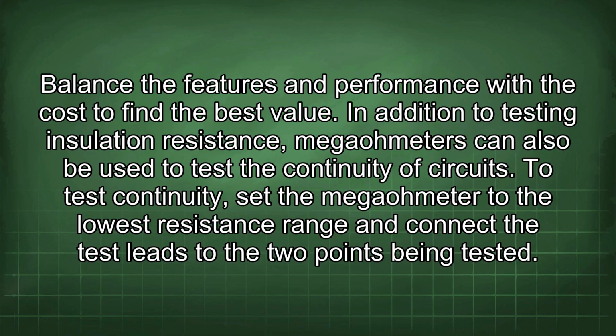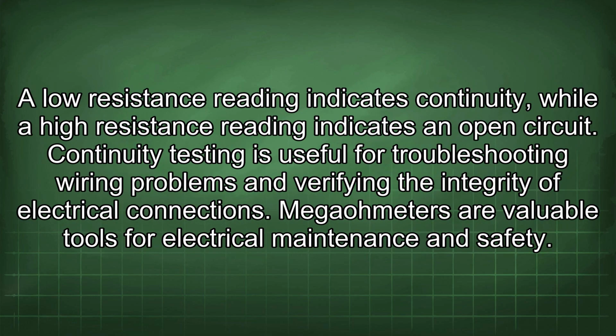In addition to testing insulation resistance, Megaohmeters can also be used to test the continuity of circuits. To test continuity, set the Megaohmeter to the lowest resistance range and connect the test leads to the 2 points being tested. A low resistance reading indicates continuity, while a high resistance reading indicates an open circuit. Continuity testing is useful for troubleshooting wiring problems and verifying the integrity of electrical connections.